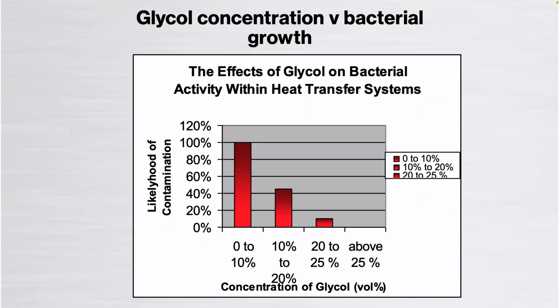But going back to bugs, and this time mixing it up with glycol. So glycol itself is great. So anything above 25% in industry is deemed to be a biostatic. Bacteria cannot flourish above 25%. Now in North America, typically you dose well above that, so shouldn't be an issue, right? However, if you've had a leak and you're not aware that you've had that leak on that system, you could be losing that. And once you go below 25% concentration of glycol or volume of glycol in your system, you could start feeding that bacteria. It becomes a food source for the bacteria.